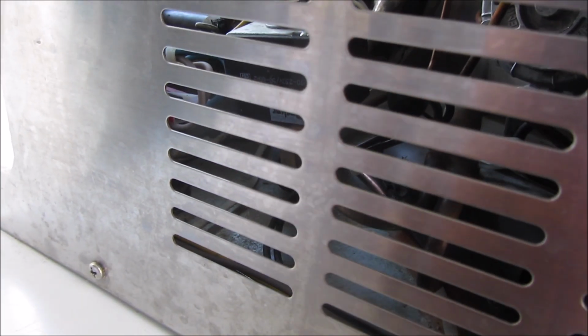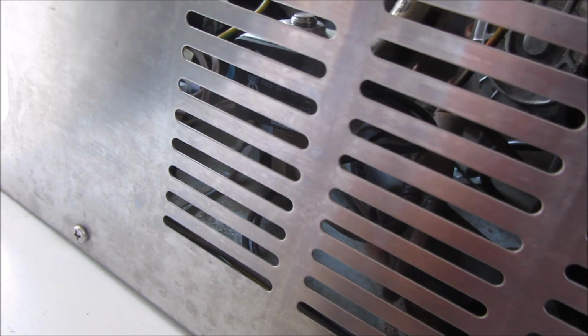It's been well maintained - this foot has been cleaned, and the condenser's nice and clean. This is just hot gas defrost: it makes ice, then hot gas defrost dumps into the evaporator to defrost it. As that happens, the water solenoid turns on, fills the reservoir again, and it goes back to making more ice, cooling the water down again, and starts over.